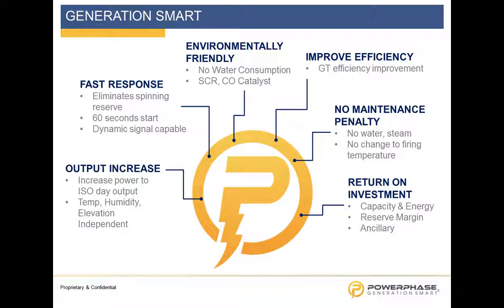But the key to this is that we don't change the firing temperature. So since the firing temperature is unchanged and we're not injecting any water or steam, there is no maintenance penalty to the gas turbine. Just if you look at your OEM factor fired hour calculations or equivalent operating hour calculations from your OEMs, you'll notice that there is zero effects of ambient temperature. There's nothing in your calculation for your planned maintenance that accounts for changing ambient conditions. And changing ambient conditions result in changing mass flow. And therefore, from that, you can understand that mass flow, as long as firing temperature remains constant, has no effect on your turbine.